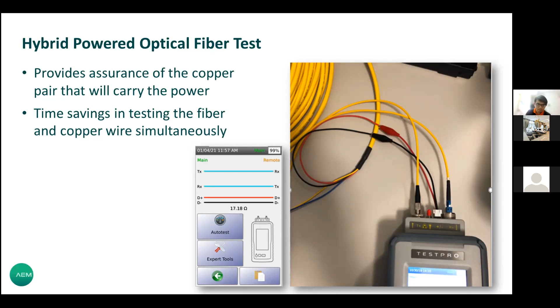So at the end of the day, after all this testing, of course, it's the report. It is important because at the end of the day, you need to have this evidence to keep as a record - whether you are a contractor or installer, you need this to provide to the end user, saying everything has been tested, that the cable can support your IT network, the cable can support your IoT devices, the cable meets PoE requirements, the cable has a good SNR ratio. So with this report, it provides confidence and assurance to the end user.